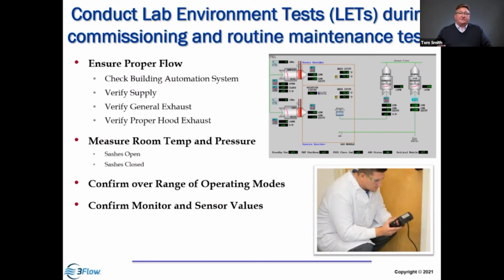First and foremost, oftentimes we look at the reporting of flow by the building automation system. What information is being reported about the operational conditions of that space? It may report the exhaust flow and the supply flow and other conditions, maybe pressurization. Well, are they right? Who knows, right? Oftentimes we find errors between the reported value and the measured value. And our measurements are what's often used to calibrate and confirm the accuracy and precision of the controls. So their reporting is only as good as our measurements.